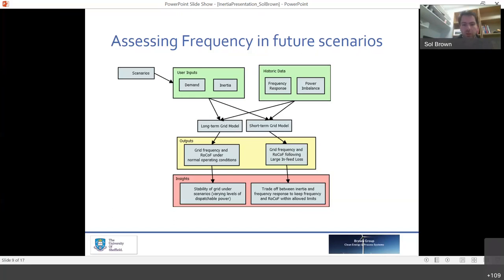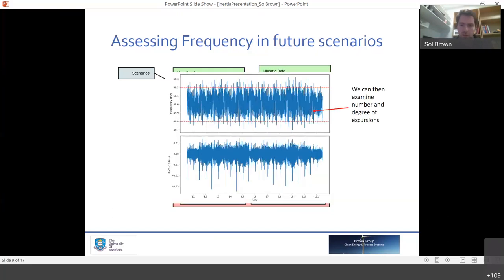And if we push this through some of our models, then we can look at the number of excursions, which don't really change a great amount under scenarios where we're dropping the amount of inertia. And we can see similarly that the rate of change of frequency is also not changing rapidly. So on a normal operating scenario, if we project forward to a scenario where we have less dispatchable power, we're still able to maintain normal operation of the system.